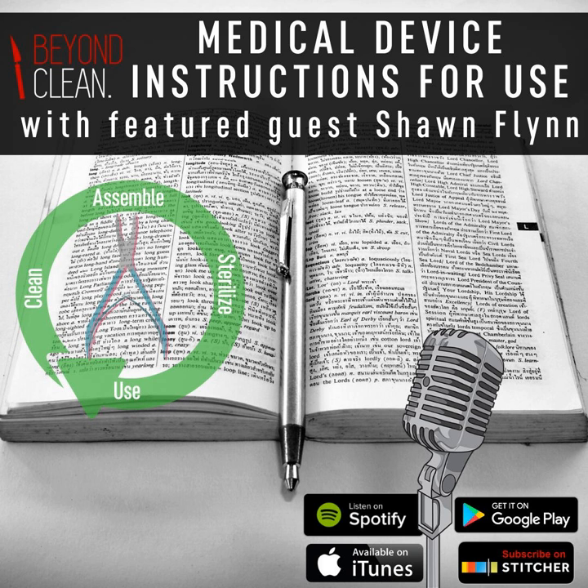For example, the reason FDA got away from doing extended cycles, or allowing extended cycles, is because people were gaming the system, changing the pulse rates of the sterilizer to pass the half-cycle steam sterilization validation. That created a hardship for sterile processing departments, because now there's not a standard number of cycles, there are many different cycles. If you're like any other sterile processing department, you might have 50 to 60 different manufacturers coming through, just on orthopedic loaner trays, between spine, ortho, and neuro. So it can get very complex, and it caused actual difficulty and uncertainty in the sterile processing or hospital world, in my opinion.